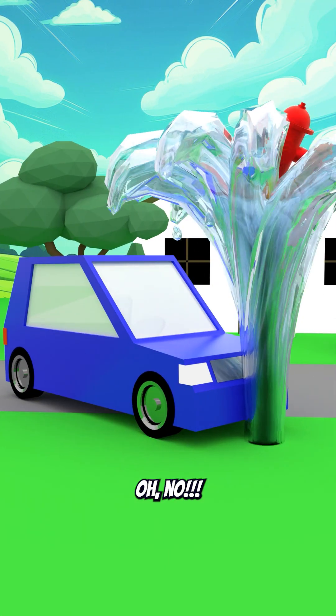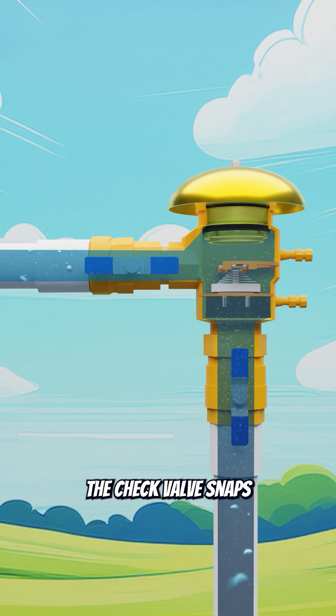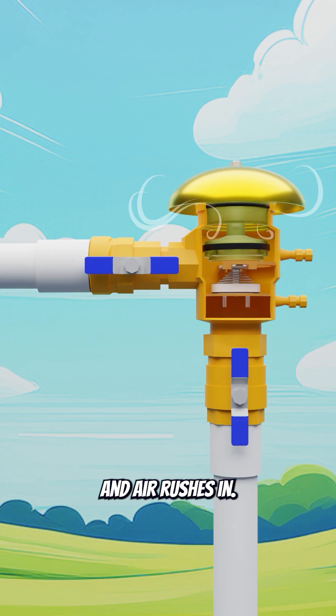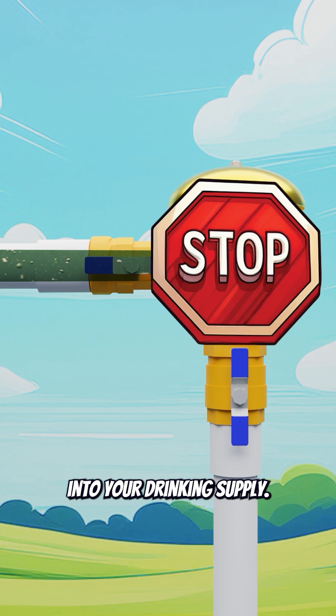Oh no! There'll be negative water pressure sucking the water in your pipes backwards. The check valve snaps shut, the poppet opens, and air rushes in. That breaks the siphon and keeps dirty, icky water from being sucked back into your drinking supply.